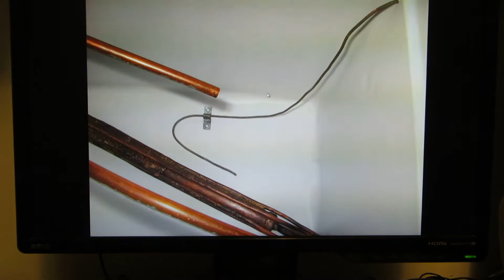Now, the reason that if your compressor stops your CPU won't get hot in a hurry is because the whole container is filled maybe about 5 inches up or so with an antifreeze mixture. So not only is the compressor cooling the fluid going through the 7/8, it's cooling the whole antifreeze mixture in here. So when the compressor gets it down to temperature, here's the last picture. That's your probe there for this. And that's just sensing the temperature of the antifreeze.